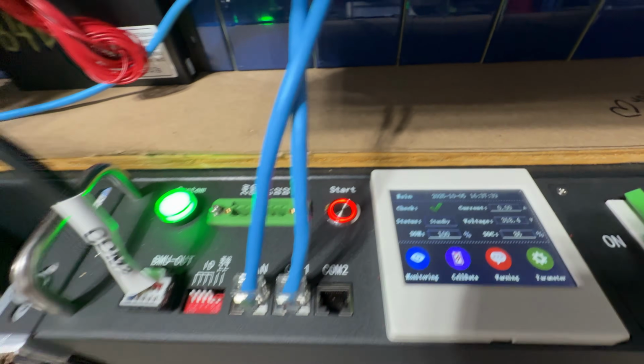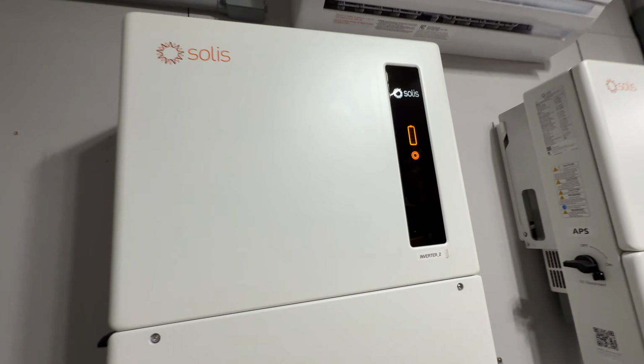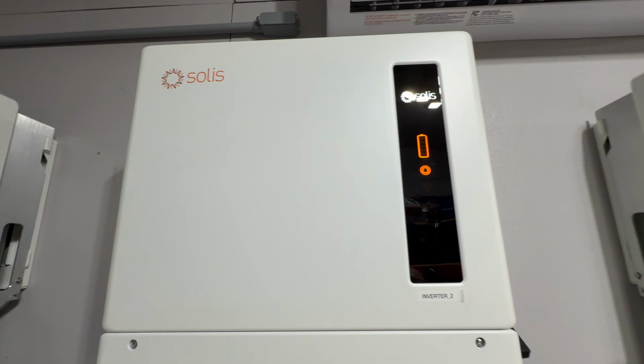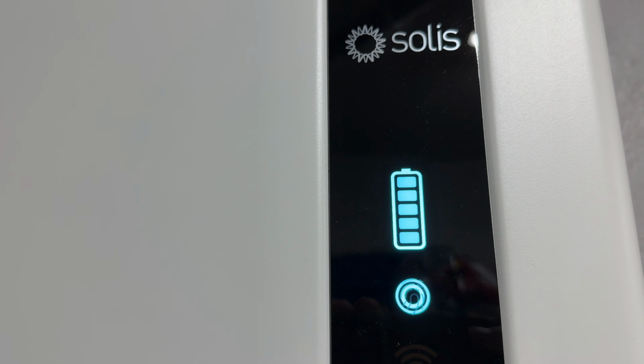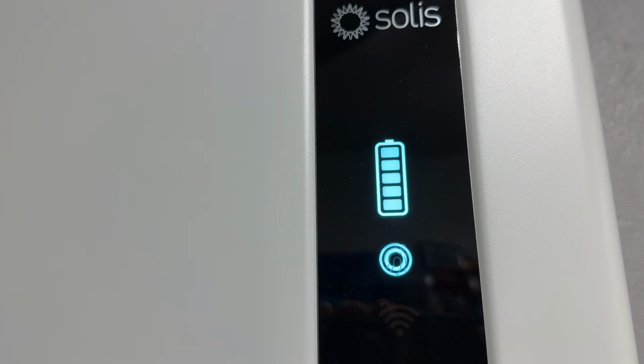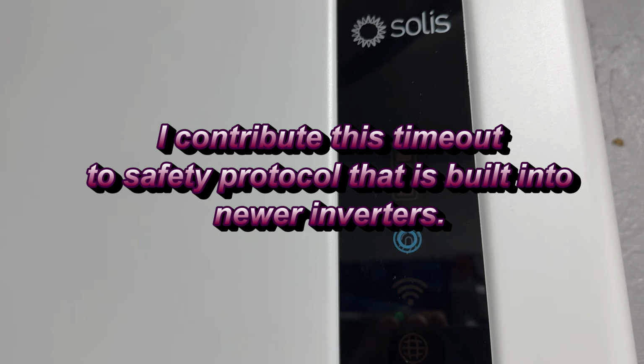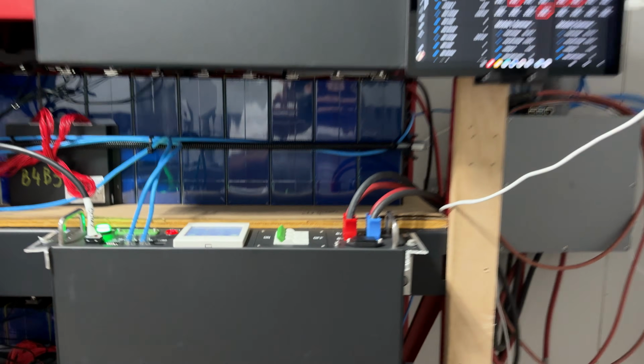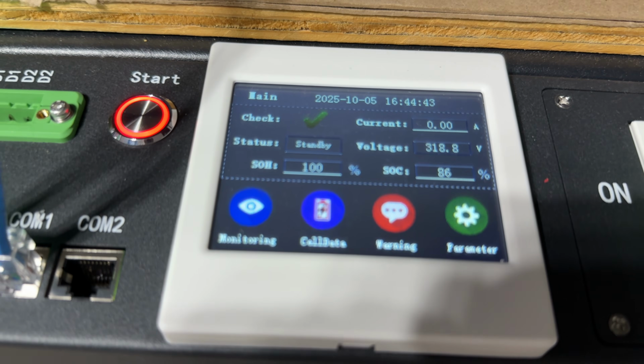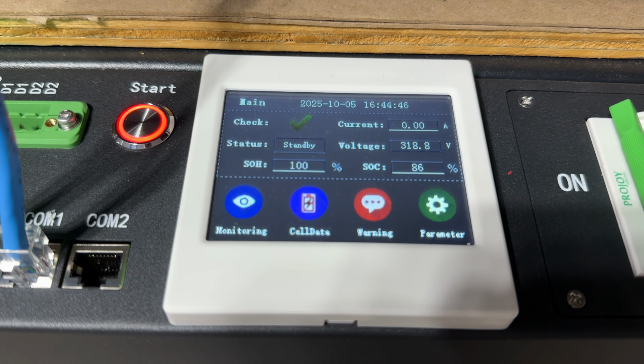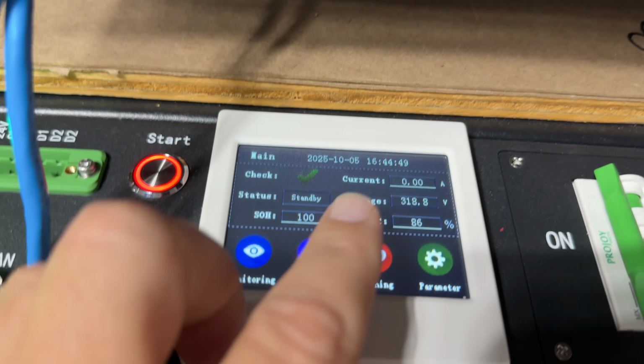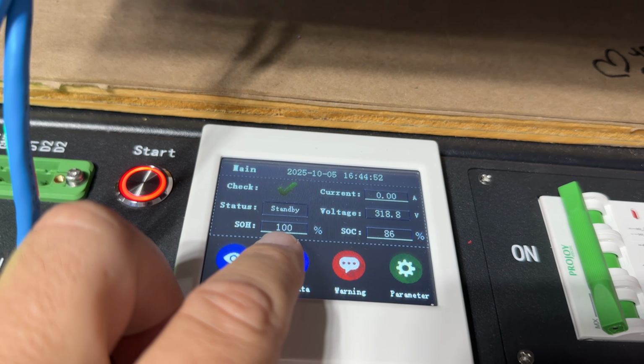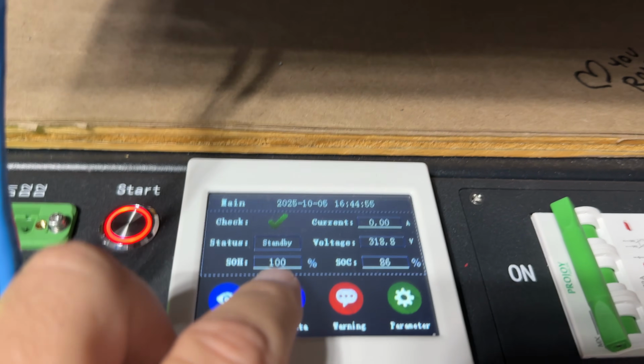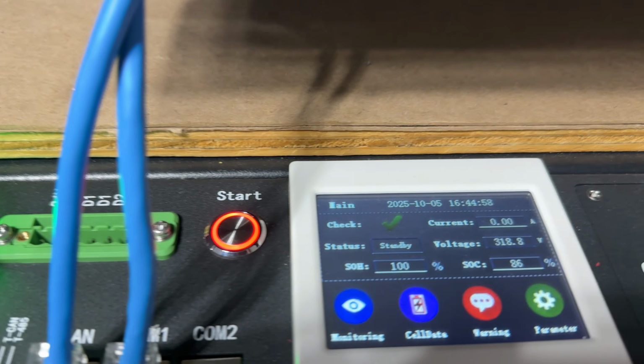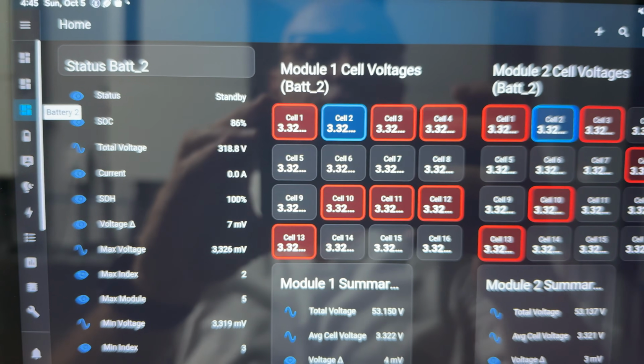It goes back into standby mode. Now it will send the CAN communication over here. Any action on these inverters takes about a 5-minute timeout. Even though I started the battery, I have to wait about 5 minutes for it to reset itself and get the inverter going again. Here we are back at the BMS itself - it's working, about 86%. The interesting point is it shows a state of health of 100%, however that is not true and it's not working, but I have found a way to deal with that.